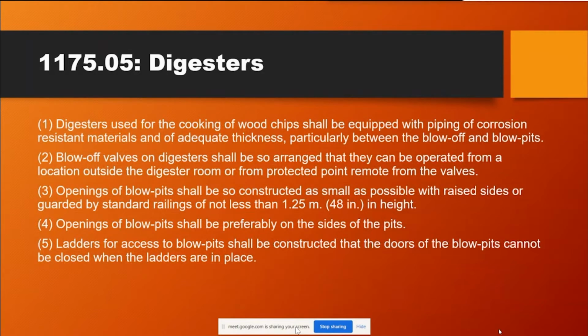Digesters used for the cooking of wood chips shall be equipped with piping of corrosion-resistant materials and of adequate thickness, particularly between the blow-off and blow pits. Blow-off valves on digesters shall be so arranged that they can be operated from a location outside the digester room or from a protected point remote from the valves. Opening of blow pits shall be constructed as small as possible with raised sides or guarded by standard railings of not less than 1.25 meter or 48 inch in height.